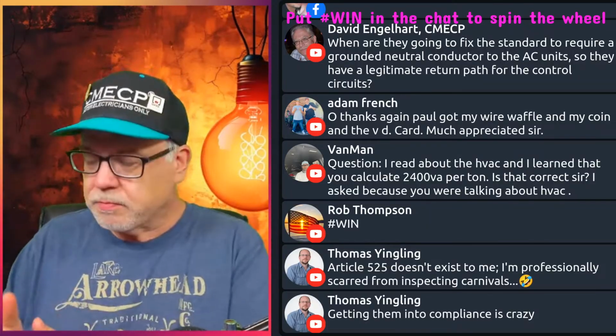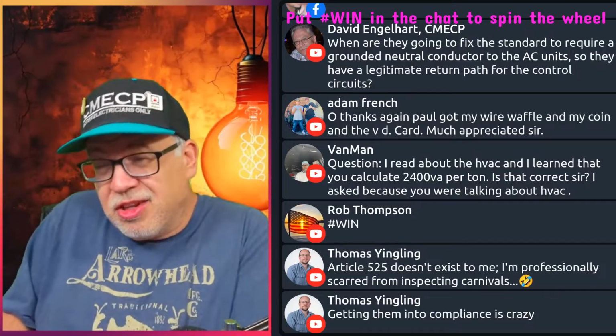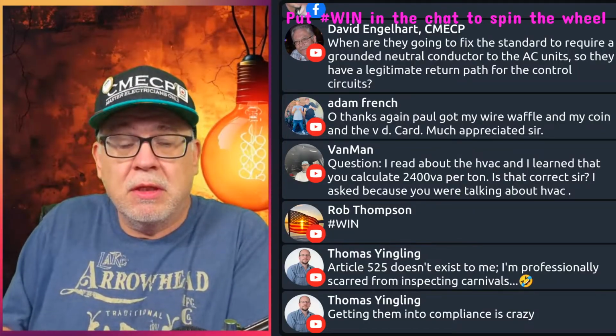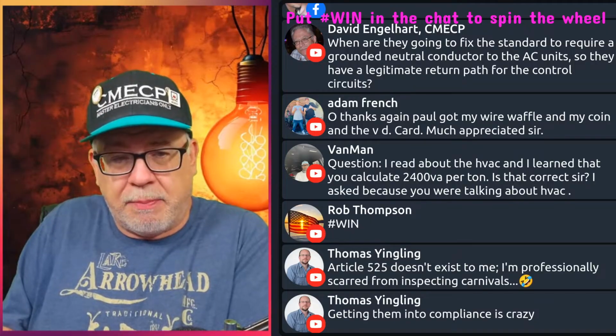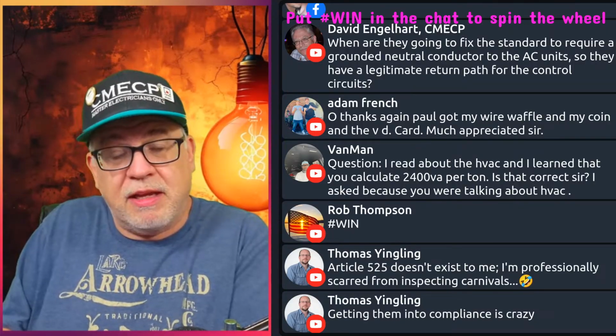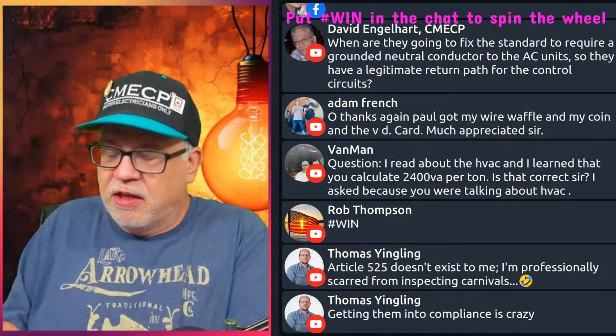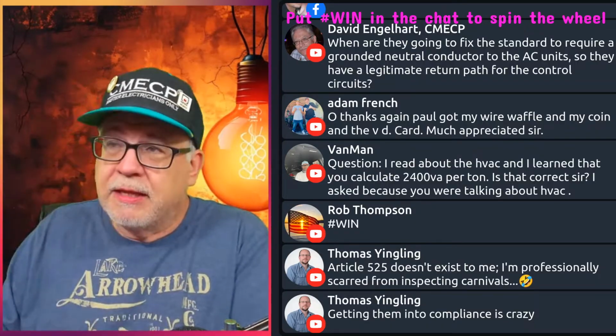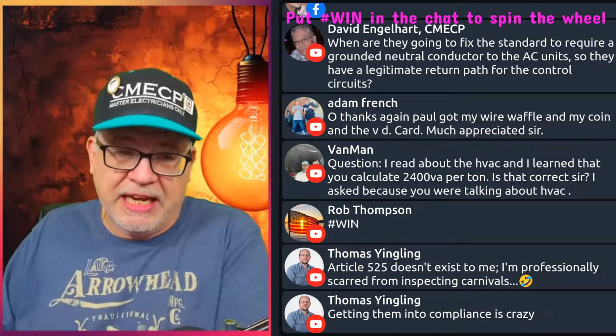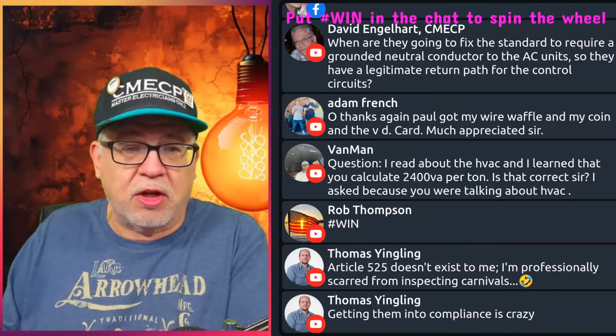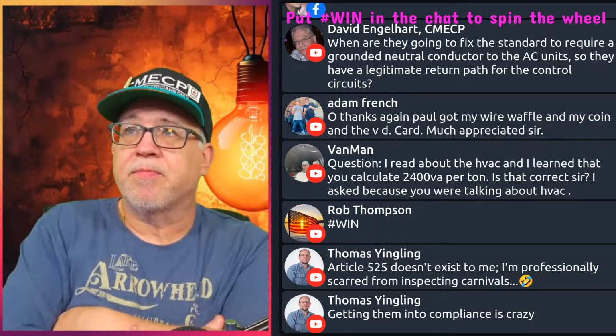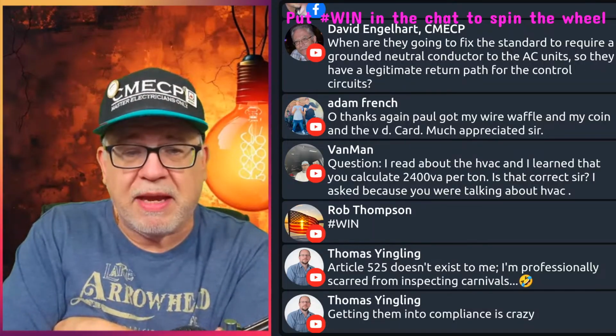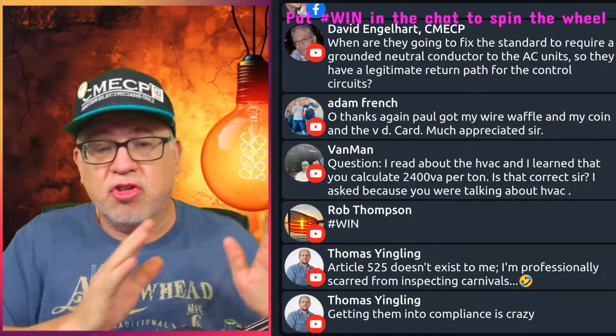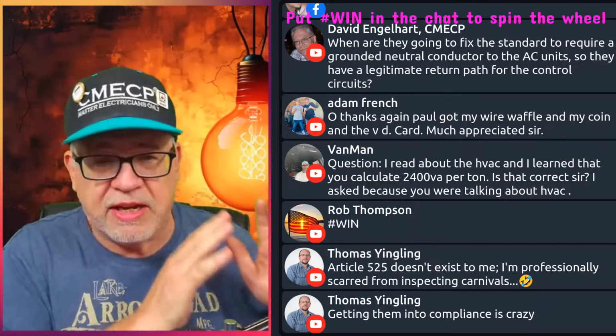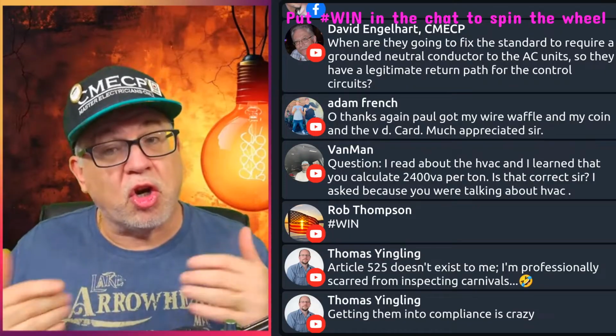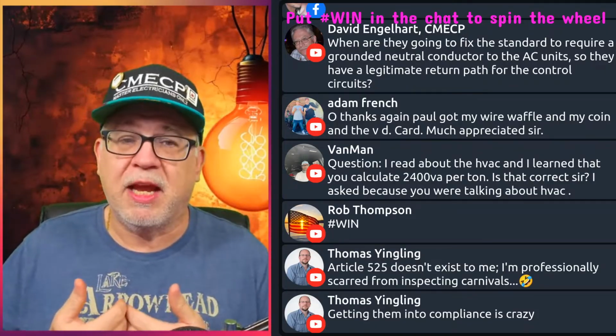Okay, so EVSE. What it looks like right now is that the cord and plug are going to have to be GFCI protected. If it's 150 volts or less to ground, it's just a Class A GFCI. If it is over 150 volts to ground, again cord and plug, then it's going to have to be an SP GFCI, okay? Special purpose. And those are typically going to go up to like 20 milliamps. Obviously, there are many manufacturers, like ChargePoint for example, who say don't put ours on a cord and plug GFCI. Hardwire it. Because currently in the code, there's no GFCI requirement for it to be hardwired.